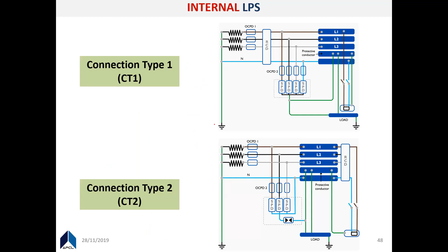For the different class types, there are SPD classes - class 1, type 1, type 2, type 3 - class or type. This is the waveform which is coming initially: 10/350, 8/20, and 8/20 residual surges. 10/350 is a high energy waveform. These SPDs are made to comply with different tests.